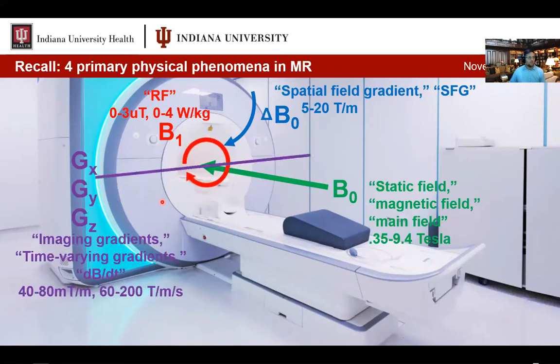Okay. And then there's, of course, the imaging gradients, which are the crazy loud things that occur and stimulate peripheral nerves in patients, and can even stimulate the brains of patients. And that's because they are changes in the magnetic field that are happening very, very rapidly, on the order of 1/100th of a second. We refer to these as imaging gradients or time-varying gradients, as we discussed earlier, dB/dt, because it's the change in the main field, B0, as there is a change in time. The typical units for these, we talk about the magnitude most often, which is 40 to 80 millitesla per meter. So that would be the slope of this purple line.